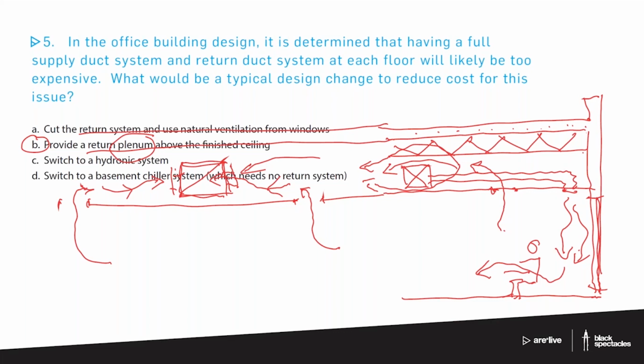That's using the ceiling space above the ceiling to get that air back. Could we switch it around and use the plenum for supply? Yes, there are lots of examples of that. You don't usually do that at a ceiling, but it's possible. Sometimes you'll see supply plenums below a floor, like a raised floor where you'd pump supply air in below and it comes up through the floor. Sometimes in theaters you'll see it below the floor to get cool air right to where people are. There are many ways plenums get used, but if you see the word plenum, this office or institutional scenario with a dropped ceiling using that interstitial space as an air plenum should pop into your head.